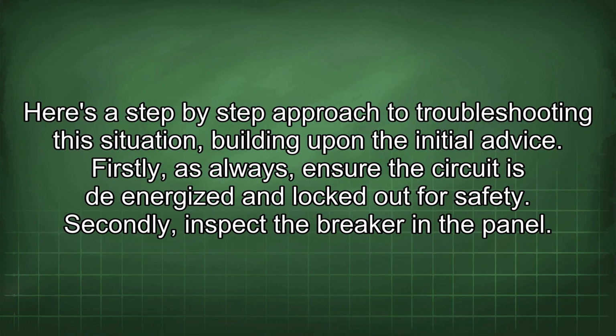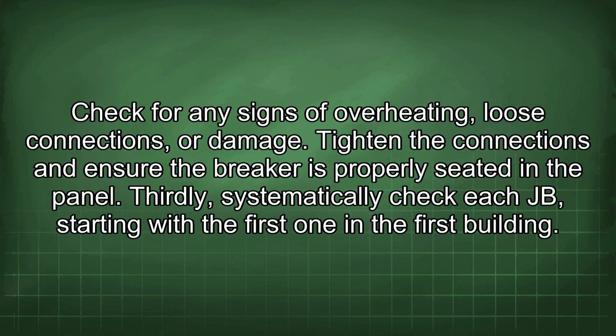Here is a step-by-step approach to troubleshooting this situation, building upon the initial advice. Firstly, as always, ensure the circuit is de-energized and locked out for safety. Secondly, inspect the breaker in the panel. Check for any signs of overheating, loose connections, or damage. Tighten the connections and ensure the breaker is properly seated in the panel.